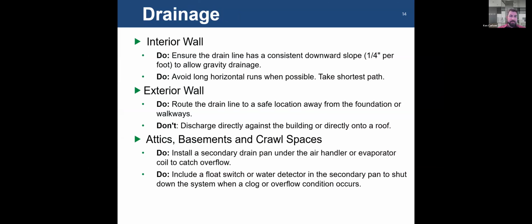Conversation on drainage. All right. Important, right? Make sure the drain lines are always sloped downward, industry standard, 1/4 inch per foot. Avoid long horizontal runs when possible, pretty straightforward. Exterior walls with drain lines to a location away from the foundation or walkways. Don't discharge directly on a building or on a roof.